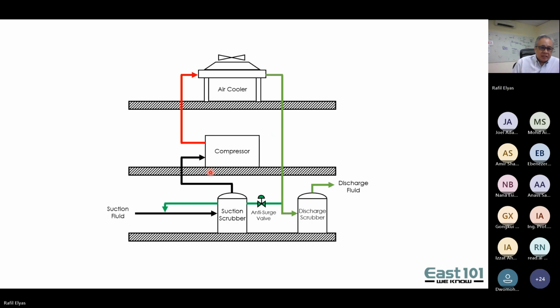Okay, earlier I showed you a simple schematic, but if I put this in a very simplified GA, a general arrangement drawing, you can see that sometimes on an offshore facility your equipment might be on different decks. Your suction scrubber might be on one deck, the compressor on another deck, and the hot discharge gas from the compressor has to go up. If it's an air cooler, it's normally at the top deck, so it goes all the way up and then comes back down again. So you've got a fairly long path. That's why sometimes you might want to bypass the air cooler and shortcut it with a hot bypass. A lot of times the effectiveness of the anti-surge loop is a function of this arrangement as well as all of the piping and valve sizes.